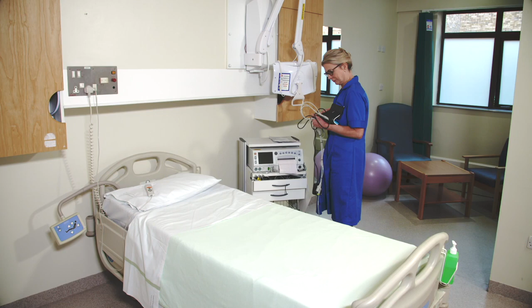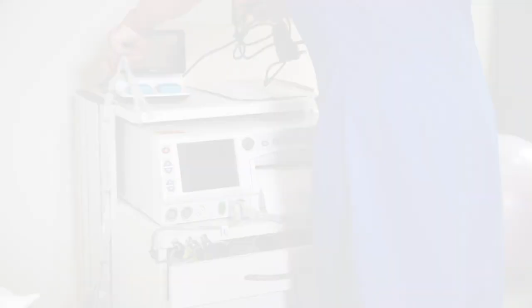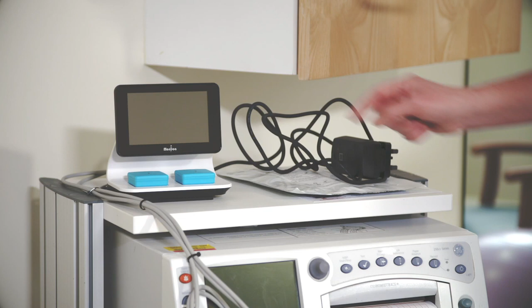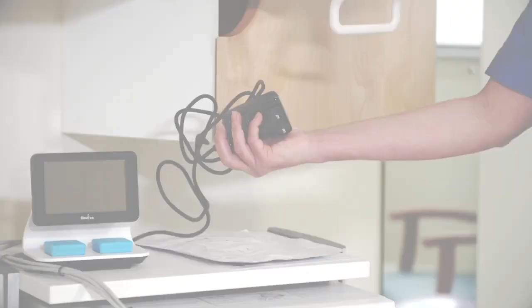Training Session 2. Setting up the Novii wireless patch system and testing. If Novii is not in the room, you will need to take one from another L&D room and find a safe place on the cart or on top of the monitor to place it. Before you start, confirm that there are 2 pods, one in each of the 2 Novii charging bays, 3 fetal monitor cables, and a power supply cord. All 4 should be connected to Novii. You should also bring with you a patch in the silver foil pouch and a roll of skin prep tape if these items are not available in the L&D room.